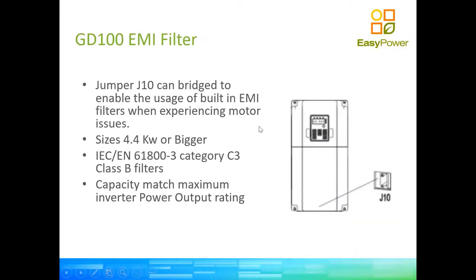Regarding the EMI filter: all pump inverters over 4.4 kilowatts — which are three-phase inverters — come with a built-in bank of capacitors. In applications with very long cable lengths, the ripple that the inverter produces on its power output can be amplified, depending on the cable length and impedance. To smooth this ripple and avoid it amplifying to a level that creates overvoltage on the motor, you can take the cover off the inverter and enable jumper J10, which puts those capacitors in parallel to the outputs, smoothing the ripple. It's similar to the water hammer effect — two waves find each other and amplify.